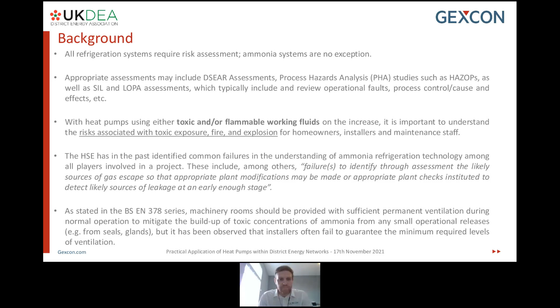One of the ways of controlling those leaks and the effects of dispersion is ventilation. We know from standards, such as the BS EN 378 series, how important mechanical ventilation is in enclosed environments to mitigate the buildup of toxic concentrations of ammonia. But ventilation also plays a key and fundamental role in the dispersion of ammonia into the ambient environment.